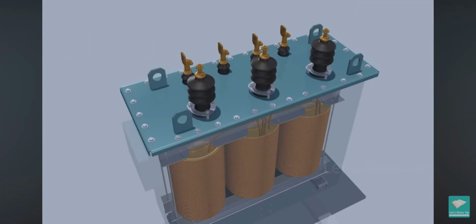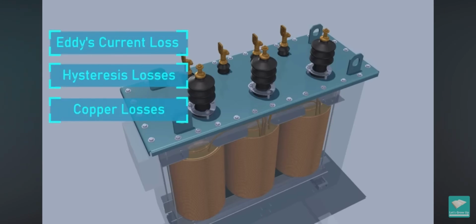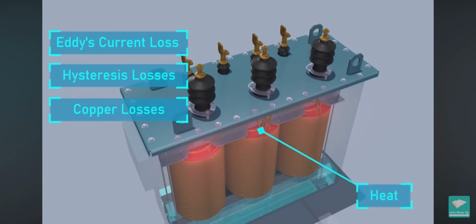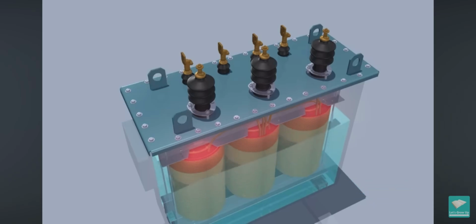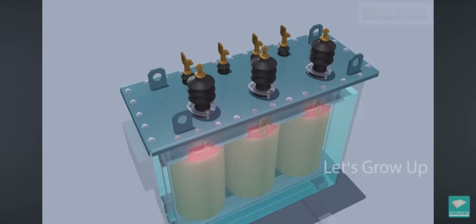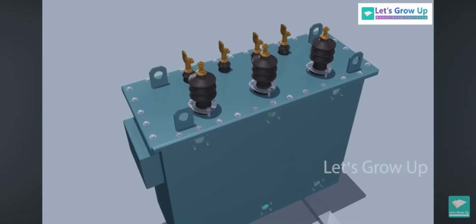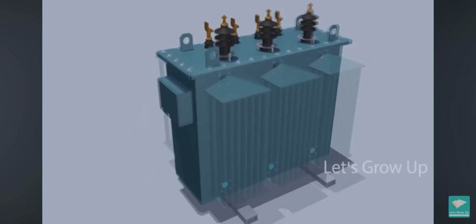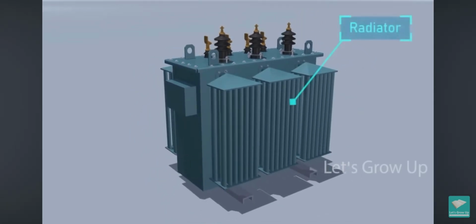During its working, or transferring the power from the primary to the secondary winding, various energy losses happen, like eddy current loss, hysteresis losses, and copper losses. All these losses generate heat. To prevent heat, transformer oil is used inside a tank. The main role of transformer oil is to act as a coolant and to insulate. Transformer oil is an exceptional heat conductor and can effectively reduce the copper coil temperature, stopping them from burning.